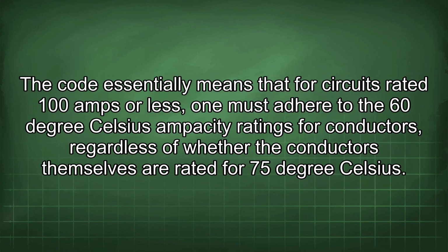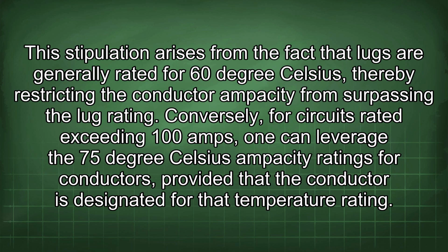The code essentially means that for circuits rated 100 amps or less, one must adhere to the 60 degrees Celsius ampacity ratings for conductors, regardless of whether the conductors themselves are rated for 75 degrees Celsius. This stipulation arises from the fact that lugs are generally rated for 60 degrees Celsius, thereby restricting the conductor ampacity from surpassing the lug rating.